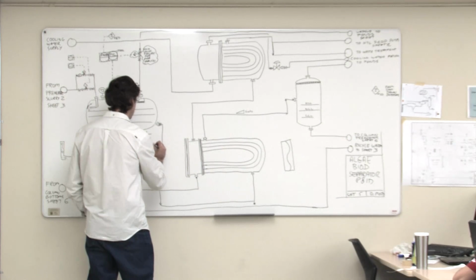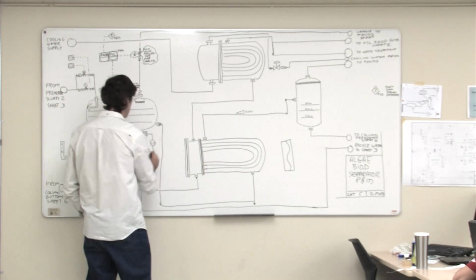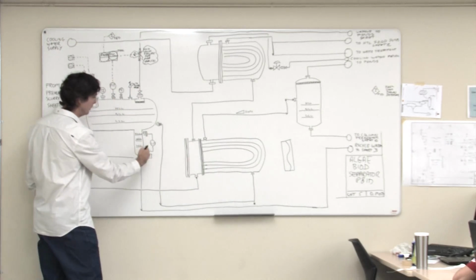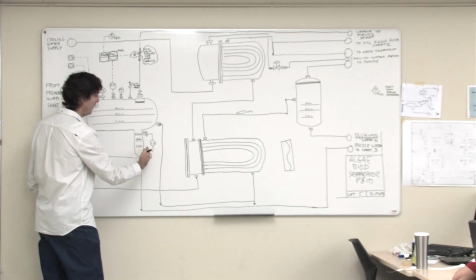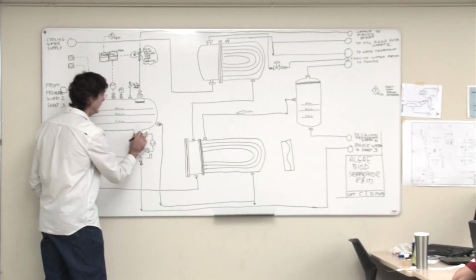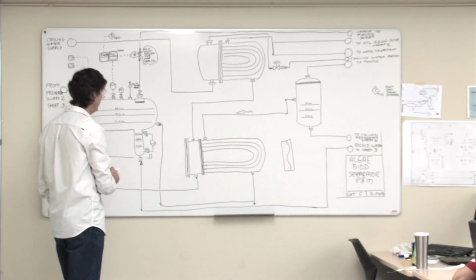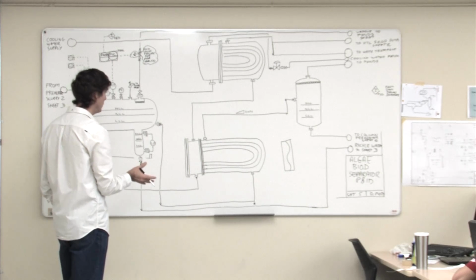Then we're into the level indicating transmitter. So on the transmitter side of the seal, it's oil filled. On the process side, it's got the water in contact with the seal. So that'll hopefully make the level transmitter more reliable.